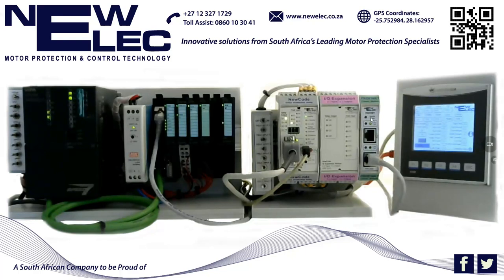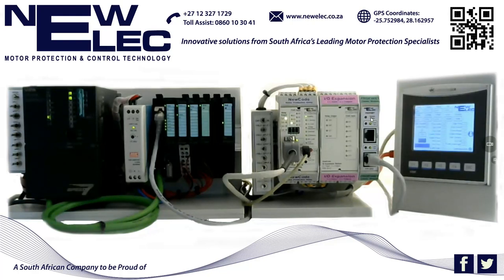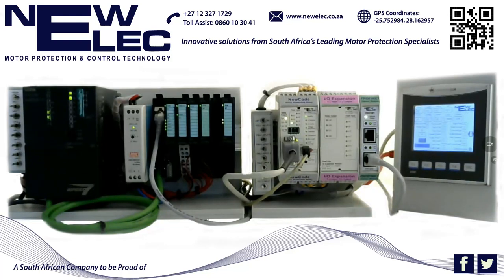The PROFINET module's address gets set up via the NewCode frontend. On the front I've got the address indicating via a tri-color LED, where green is the 1s, red is the 10s, and orange is the 100s.